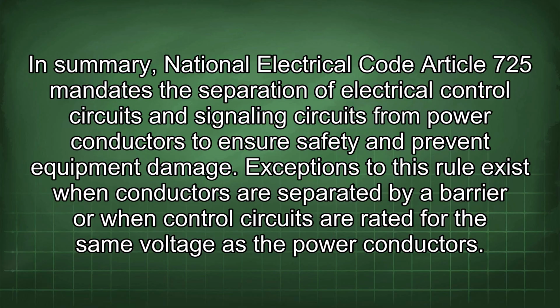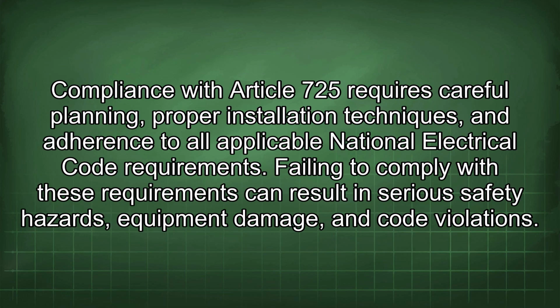In summary, National Electrical Code Article 725 mandates the separation of electrical control circuits and signaling circuits from power conductors to ensure safety and prevent equipment damage. Exceptions to this rule exist when conductors are separated by a barrier or when control circuits are rated for the same voltage as the power conductors. Compliance with Article 725 requires careful planning, proper installation techniques, and adherence to all applicable National Electrical Code requirements. Failing to comply with these requirements can result in serious safety hazards, equipment damage, and code violations.